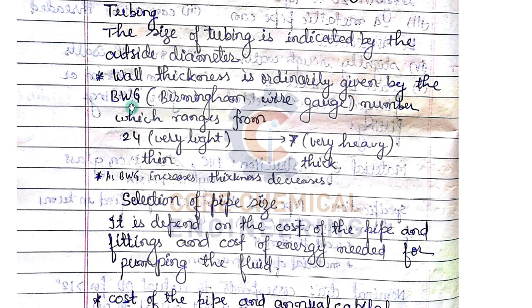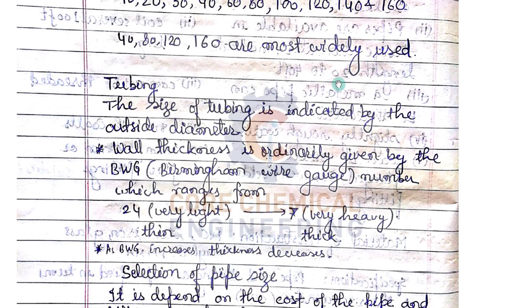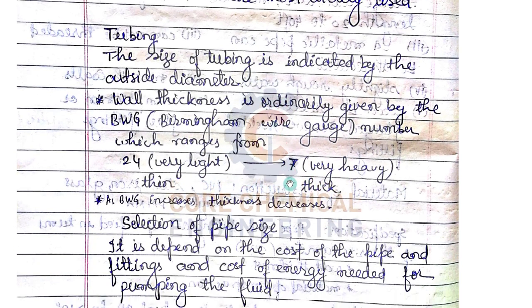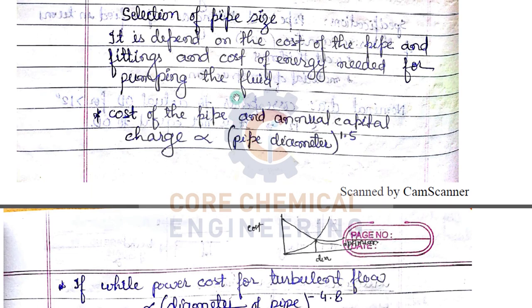The size of tubing is indicated by the outside diameter, wall thickness is given by the BWG (Birmingham Wire Gauge) number, which ranges from 24 (very light) to 7 (very heavy). As BWG increases, thickness decreases — the opposite of schedule number, where increasing schedule number means increasing thickness.